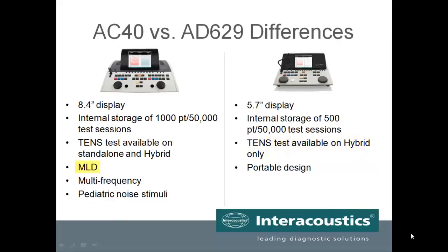The AC40 also has the capability of masking level difference testing and multi-frequency. A new test stimulus now available through Interacoustics is the pediatric noise stimulus, labeled as PED. This is a narrow band noise signal designed with very steep filter slopes, and it replaces the use of narrow band masking noise as a stimulus for threshold assessment, in particular for pediatric testing and in sound field VRA testing.